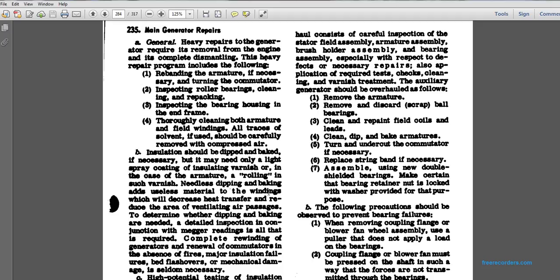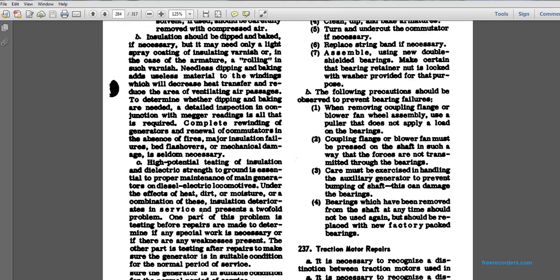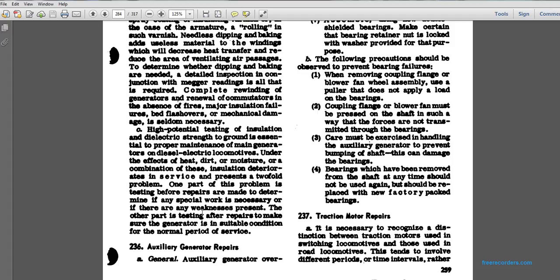required. Completing the rewinding of the generators, renewing the commutator, the absence of fires, insulation failures, and flashovers, mechanical damage, and the like is seldom necessary. High potential testing of insulation, dielectric strength, and grounding is essential to the proper maintenance of the main generator on a diesel electric locomotive. Under the effects of high heat and dirt and moisture, and a combination of these, insulation deterioration in service presents a twofold problem.